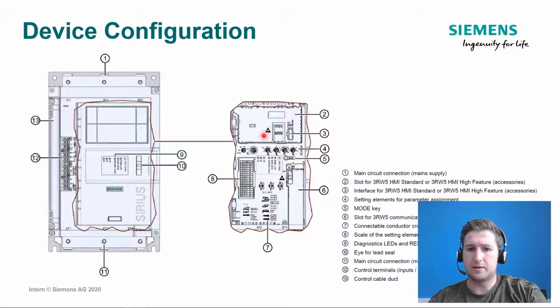Over here, number 2, you've got a slot for an HMI screen. As I mentioned earlier, and we'll discuss a bit more later, you have the option to have either a basic HMI or a standard HMI fitted into this slot. Number 3, this is where you plug the ribbon cable that connects the HMI. Number 4, these are the potentiometers which are used to parameterize the device itself. In there you have a pot for the overload, the operational current of the motor, a ramp up time, current limit function, starting voltage, and a ramp down function.